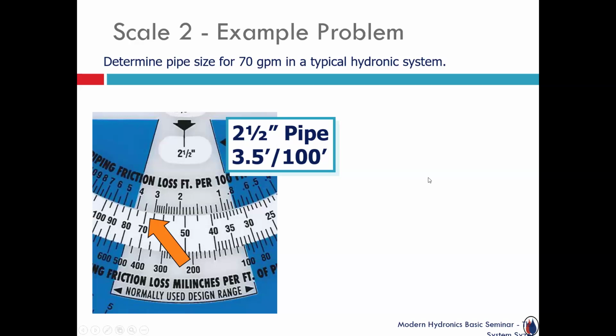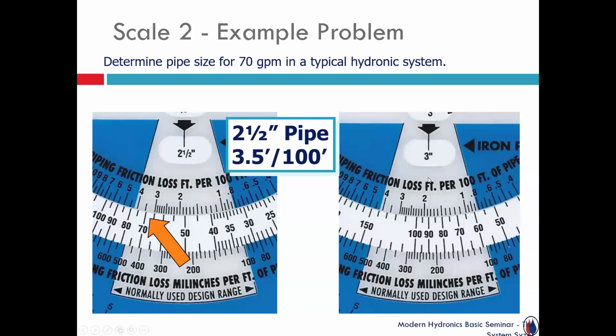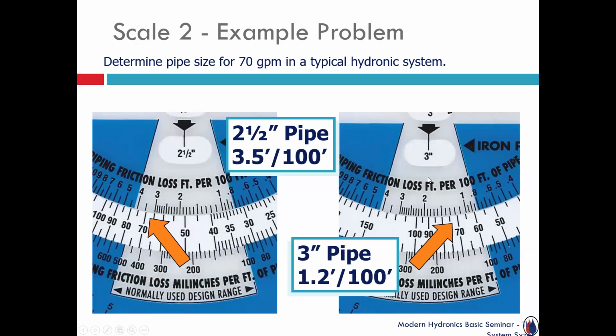And this is one of those examples where you might actually have two answers. In this case, 2.5-inch, a little higher pressure drop, but still it's acceptable. But as I move that scale and that wheel on scale 2, I also see that 3-inch iron pipe size, and that 70 continues to fall within that triangle. It's just obviously to the right-hand side. And when I look at it, it's telling me it's only creating about 1.2 feet of pressure drop for every 100 feet, which makes sense. Same flow rate, 70, through a certain diameter or a little bigger. One's going to have a little more resistance.